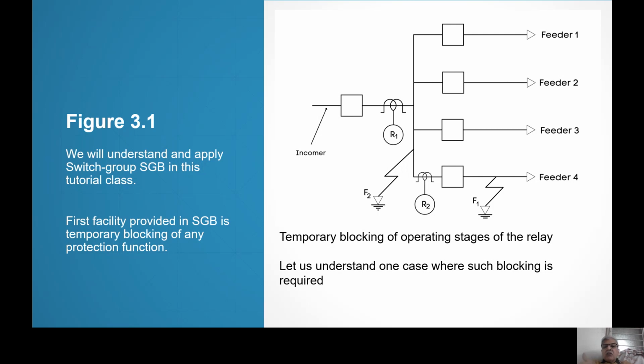So, but that was the fate. We had no other go. We did not have relays available at that time. Now in this numerical world, that is possible. What is possible? That for fault F1, say I have decided the time of operation of R2 as 0.1 second, 100 millisecond, right? Now, the best algorithm, the most accurate algorithm takes one cycle to sense the fault. So within 20 millisecond, relay R2 will sense the fault at F1. It is going to operate after 100 millisecond, but it will sense within a cycle.